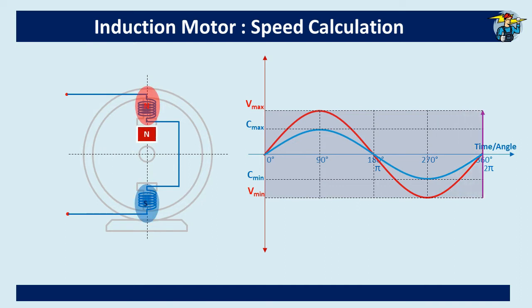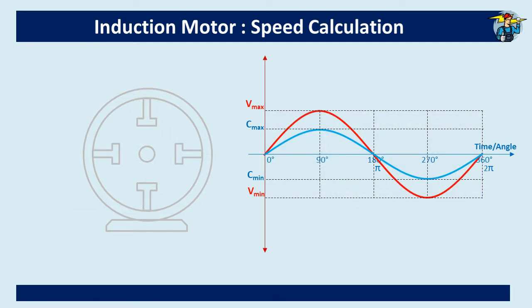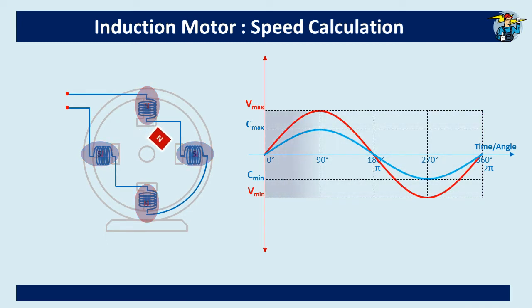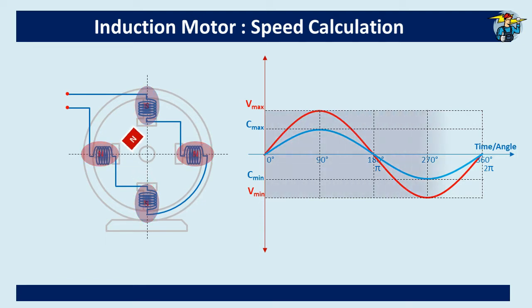Now consider a motor with four poles with a winding arrangement on all poles. When the voltage sine wave completes one full cycle, the magnetic field rotates only half of the circle. For the magnetic field to rotate a full 360 degrees, it needs another voltage cycle, because of the additional pair of poles introduced. When you double the number of pole pairs of a motor, the synchronous speed becomes half the speed of the voltage cycle rotation.